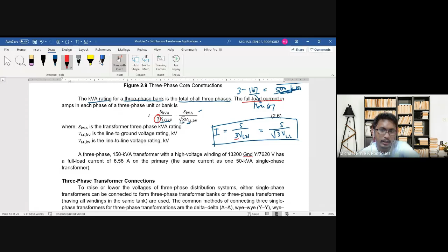Same formula, this comes from your three-phase circuits, AC circuits, Circuits 2. So same thing, you have S in kVA over 3 times your line to neutral or line to ground, also equal to S divided by square root of 3 times line to line. Take note, the multiplier is 3 when line to neutral or line to ground, and square root of 3 when line to line.